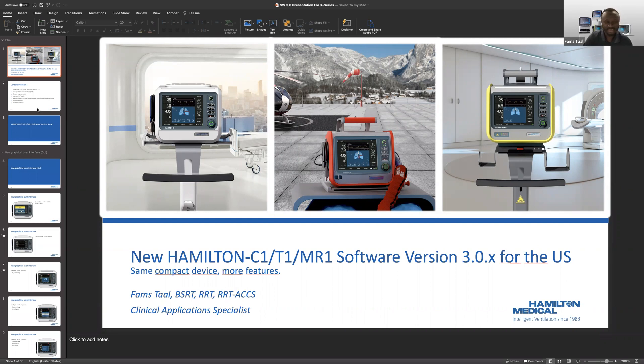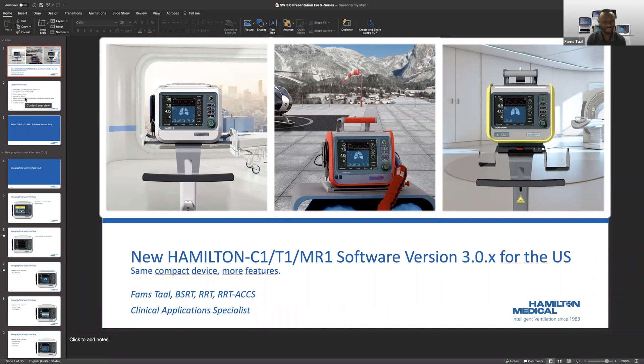The purpose of this — I know you guys have some vents coming that have the newest software and some that don't have the newest software, 2.0 we call it. It's not a major update that requires ventilators to go back and get immediate updates. You might have two different platforms that look a little different. If you're looking to update any of your 2.0 vents to 3.0, there's a charge for it. However, my recommendation would be: when a tech comes out your way to do any sort of service on these ventilators, they can make the change at that time without any additional charge, since they'll already be on site.